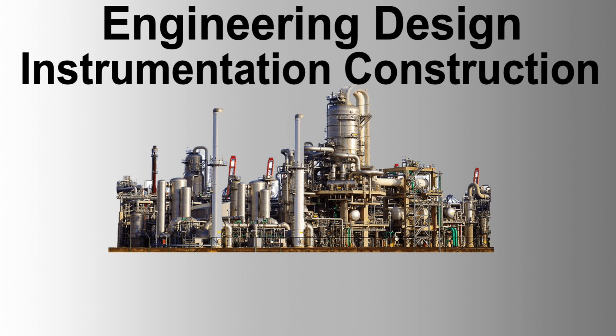This label shall not be fixed to the instrument and can be stainless steel. The contractor shall ensure that the nameplates or metal tags installed on all instruments by the vendors are intact at the completion of the installation work and are correct in accordance with instrument data sheets. Where an instrument or control valve, etc. is lagged, nameplates shall be attached by use of U-bolts and brackets, and not fitted to the lagging. Materials of the nameplates shall be stainless steel.